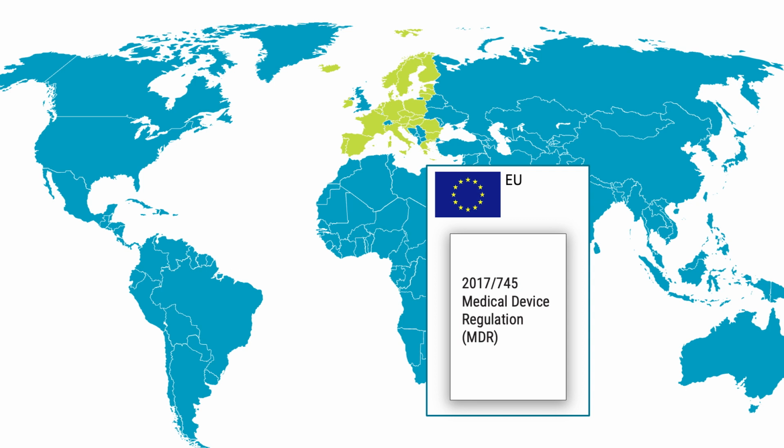And the European representative also needs to have a PRRC, and that person cannot be the same person for both those roles. And if you are a manufacturer having a notified body, it's mandatory for that notified body to control that your PRRC has the right education and training, like a certificate from a specific PRRC course.